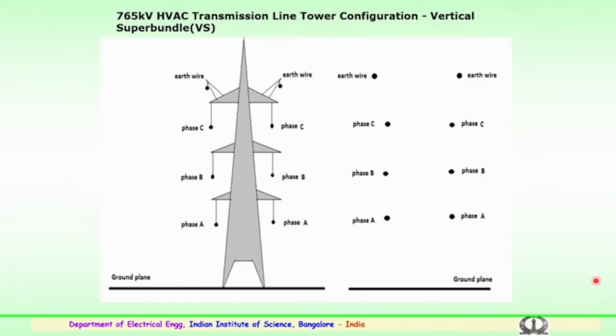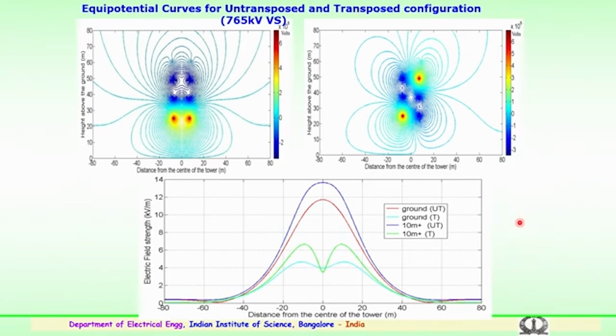So, this is again a typical 765 kV transmission line tower configuration for vertical super bundle. You can see 2 circuits here, ABC and again here ABC, and you have 2 earth wires for lightning, and the tower schematic here. This is the ground plane. Intentionally the earth wires are connected here, and you see the ABC phases are changed, and a proper transposition is done so that the advantages for transmission are better, and also there is a reduction of the electric and magnetic fields to a certain extent in case of the conductor carrying more current. So, these are some of the magnetic field and electric field values which have been simulated using developed software.